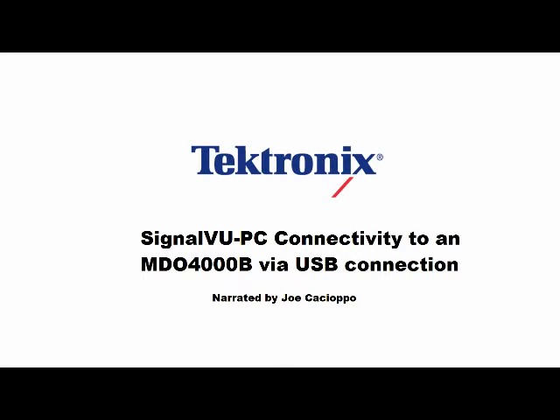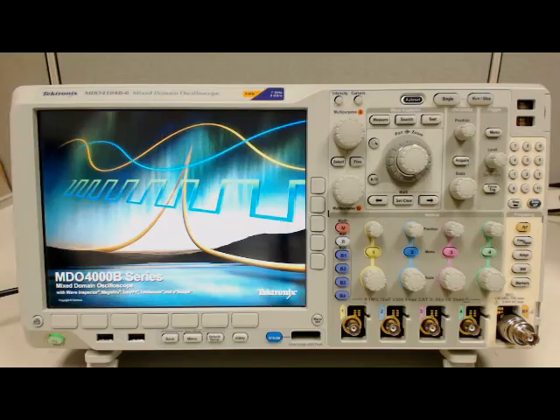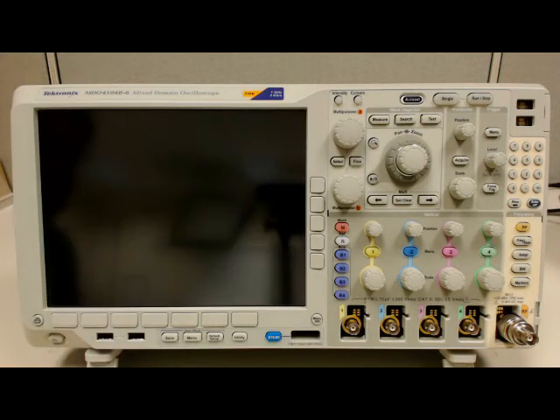The exact equipment and software versions used in this video will be displayed in text at the end of the video. To establish a connection, you will need some equipment. For this example, I am using a PC running the 64-bit version of Windows 7. You can find a complete list of compatible operating systems on the release notes for SignalVU-PC found on the Tektronix website. In addition to a PC, I am using an MDO-4104B-6 oscilloscope with firmware version 3.14 installed. You will also need a power cord to power your scope and a USB cable to establish communication to your PC.